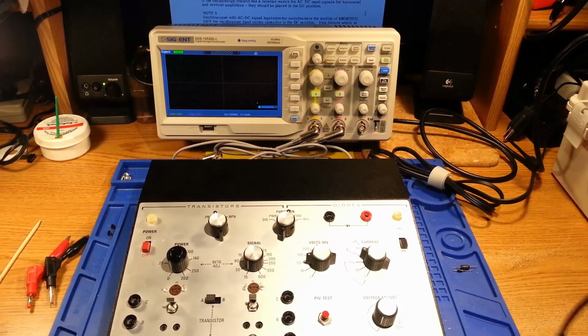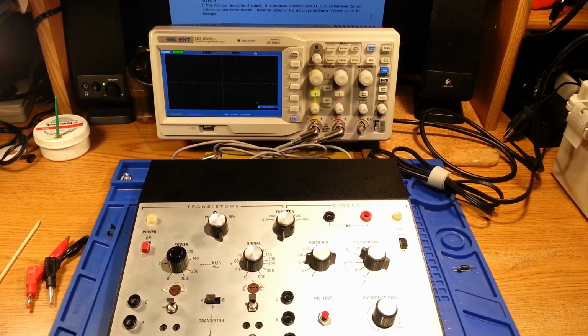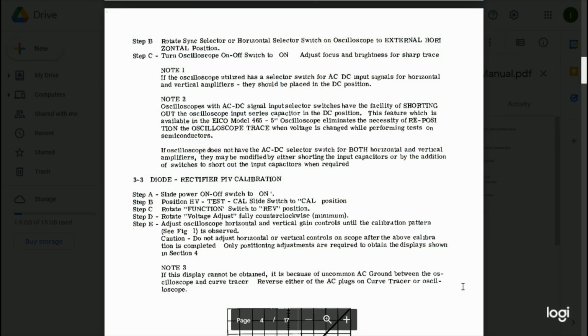So we've got that part of it going on, and then after that we have to go through some calibration functions. Now we've got the rectifier PIV calibration. So slide power switch from off to on. Well, I've got the scope set up in XY mode. I have it currently set to 1 volt vertical, 1 volt horizontal positions. The thing about this particular scope is it limits the size of the sweep on the signal to about 10 centimeters wide by 8 centimeters high, so it's not for your two axis inputs.